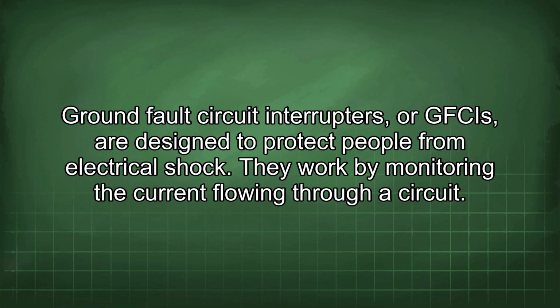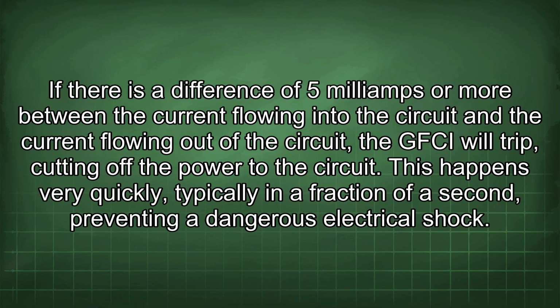Ground fault circuit interrupters, or GFCIs, are designed to protect people from electrical shock. They work by monitoring the current flowing through a circuit. If there is a difference of 5 mA or more between the current flowing into the circuit and the current flowing out of the circuit, the GFCI will trip, cutting off the power to the circuit. This happens very quickly, typically in a fraction of a second, preventing a dangerous electrical shock.